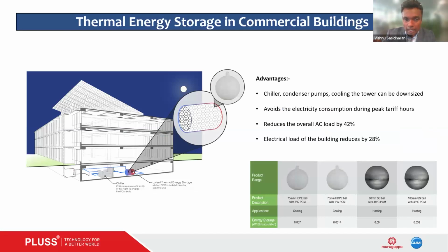Thermal energy storage systems are designed in the early stages of building design, and can play a role in reducing not just the refrigeration units but also downsizing the electrical connected load, which impacts overall connected load demand charges. So the monthly energy cost an HVAC cooling system incurs can be reduced by as much as 25-28%, when you reduce the refrigeration system by 50%.